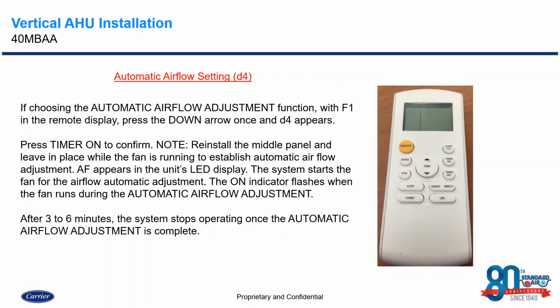Okay, this process takes about 3 to 6 minutes. After the system stops operating, you will see the fan ramp down and everything shut down, and that's how you know this automatic airflow adjustment is complete. Once that's complete, of course you're going to go back in, run the system in cooling, and take a delta T reading to ensure your charge is correct. A 20 to 30 degree delta T in cooling is an acceptable range. If we're running in heating, we're looking for a 30 to 40 degree delta T to ensure that that charge is correct.